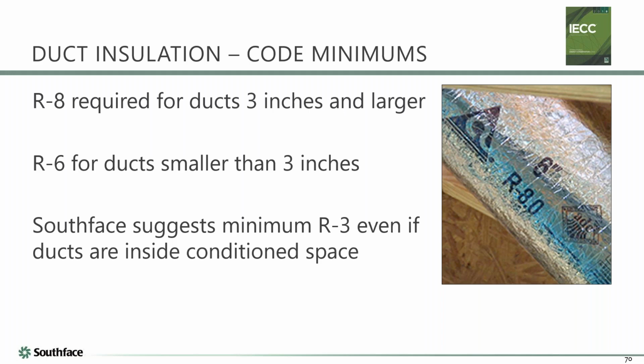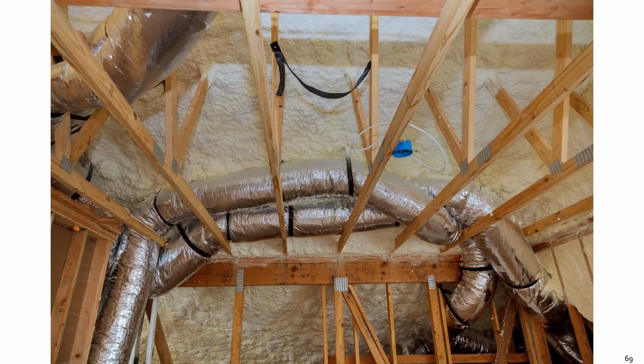And this one, good point, someone had asked about this in the Q&A here. So R8 for anything 3 inches and larger, R6 for less than 3 inches. I think R8 is probably just a good practice. And then even if you have a duct system that's going inside a conditioned space, such as a spray foam roof line that we looked at earlier, then go ahead and put some insulation on that anyway.